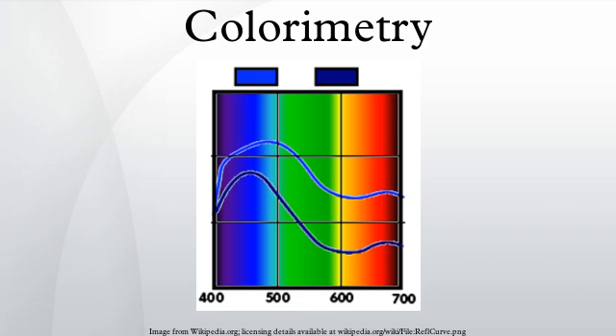One benefit of spectrocolorimeters over tristimulus colorimeters is that they do not have optical filters, which are subject to manufacturing variants and have a fixed spectral transmittance curve until they age. On the other hand, tristimulus colorimeters are purpose-built, cheaper, and easier to use.